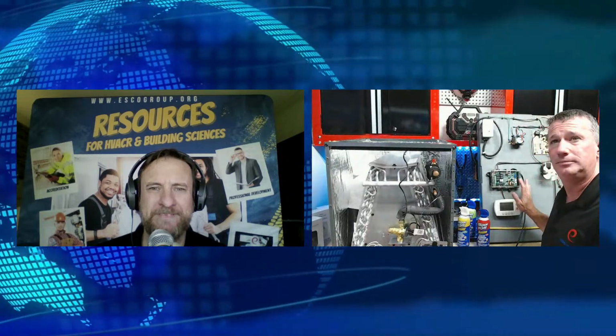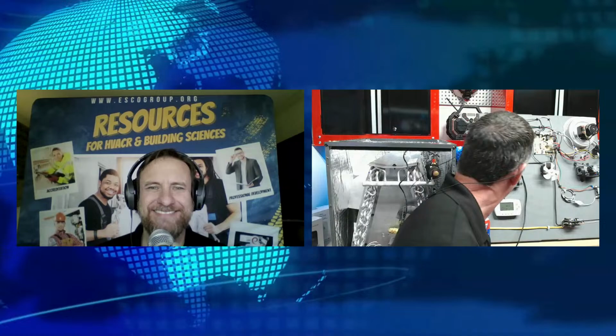This particular one here is called the Daikin Dragonfly. It is an intermediate control board that goes, exactly like we said, between our thermostat and our original indoor control board. This could also have been a retrofit system where I had a functional, modern gas furnace with an ECM blower motor, not a PSC, and I am now wanting to put an A2L system on there with an AHRI matchup. So what I can do is use our intermediate board between the thermostat and our existing furnace's control board, and I can now do all of these sequences of mitigation for a piece of equipment.